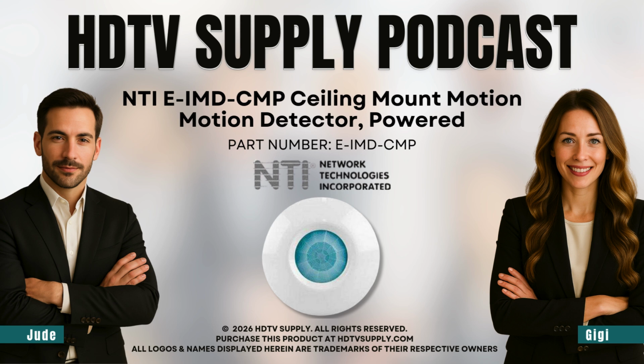How much space are we talking about? If you mount it, say, 12 feet up, which is pretty standard for a data center, it covers a diameter of 36 feet. That's a huge amount of floor space for one unit. And the key is its immunity to environmental chaos: server fan vibrations, HVAC cycling, plus really good RFI protection. With all the radio frequency interference from racks of servers, that's a huge deal. You can't have signal noise triggering false alarms.